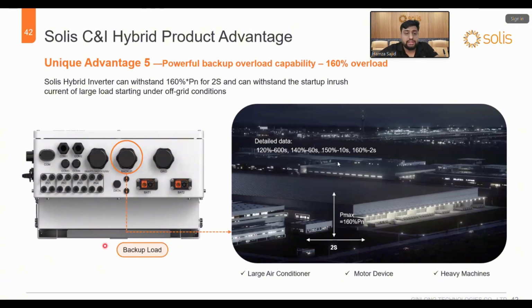Actually, when we are dealing with industrial grid systems or C&I systems, the load is also going to be high. So the fifth unique advantage is the powerful backup overload capability up to 160%. Okay. The Solis hybrid inverter can withstand 160% of the rated power for 2 seconds, which handles the startup inrush current of large loads like air conditioners, motor devices, or heavy machinery.